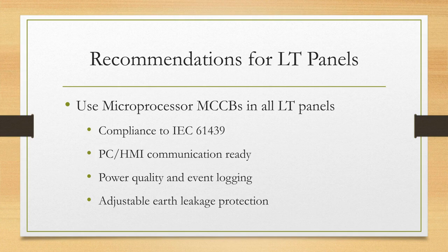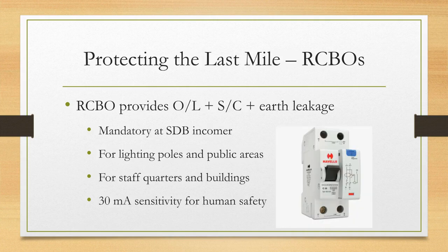For LT panels, we recommend using microprocessor MCCBs and ensuring compliance with IEC 61439. Features should include PC/HMI communication, power quality and event logging, and adjustable earth leakage protection. To protect the last mile, RCBOs are mandatory at the sub-distribution board incomer and in areas like lighting poles, public areas, and staff quarters. RCBOs provide overload, short circuit, and earth leakage protection with 30 milliamperes sensitivity for human safety.